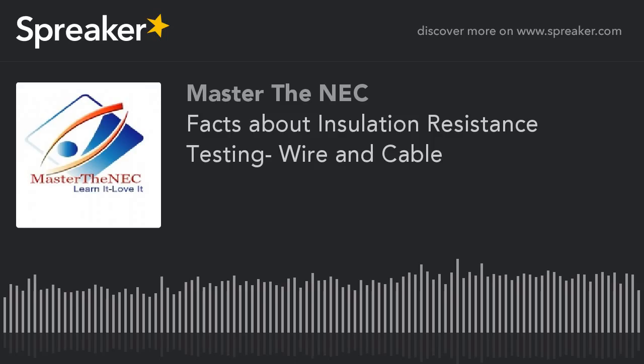It is not reliable. So that brings me to the 2 to 99 megohm rule. From 2 megohms to 99 megohms, the wire and the cable is probably acceptable. You have to look at it and see what the conditions are. So when somebody calls me and says, Paul, I got a reading between 2 and 99, say it's 50 megohms.